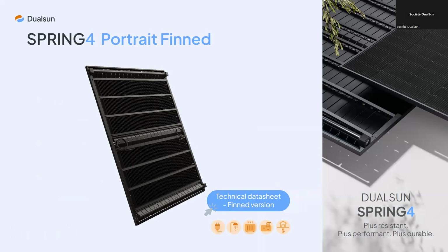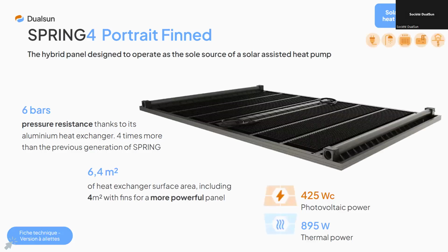Here, the purpose of the fins you can see here is to capture the energy from the air at night, because since we're trying to meet constant heating needs, both at night and during the day, we also need to be able to provide calories at night and during the day. This panel has been designed to be the sole source of heat for the heat pump. These fins provide 20% more thermal power than the classic version, the non-insulated version without the fins, and also triple the surface area of the equivalent heat exchanger, which uses three sources of energy: the sun and the roof during the day, and the air at night.